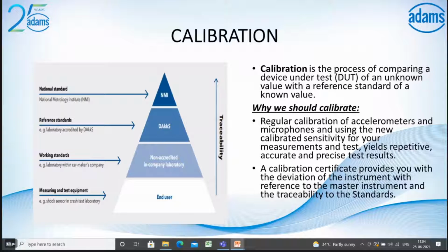For obtaining accurate and precise measurement results, the instrument must be traced to the national standards, and the traceability needs to be ensured and maintained by the calibration hierarchy. It should be traceable to national standards such as the NMI. For Germany, it's PTB, and for India, it's NPL. Then the reference standards: it's a laboratory accredited by DAkkS, the German accreditation body. In India, it's NABL, the National Accreditation Board for Testing and Calibration Laboratories. Then the working standards: it is a non-accredited in-company laboratory.